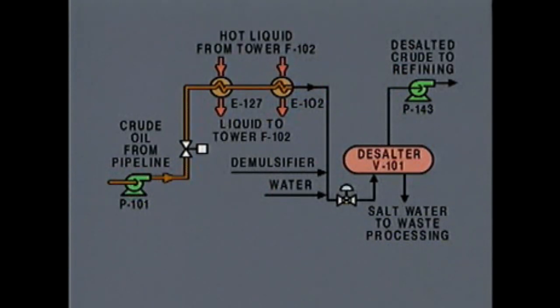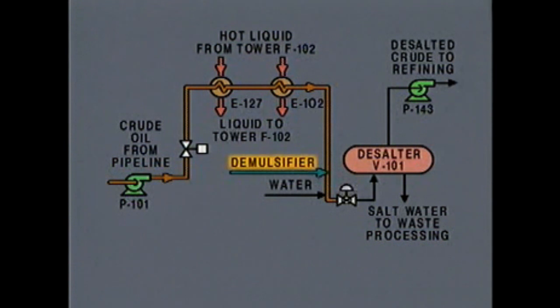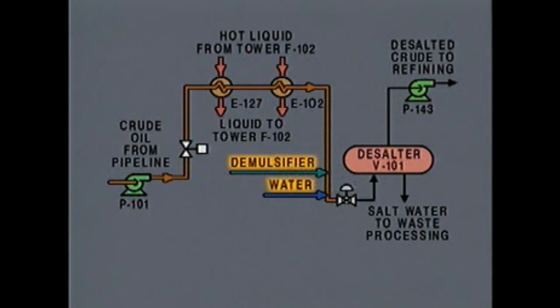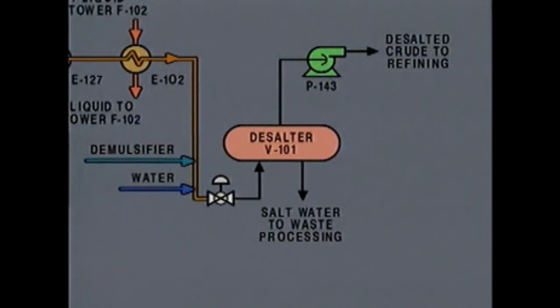As we trace the oil flow leaving heat exchanger E-102, we see that it flows past a demulsifier addition line and a water addition line. The demulsifier and water are added to the oil to help the desalter do its job. Next, the oil goes through a control valve that's operated by a pneumatic diaphragm actuator.